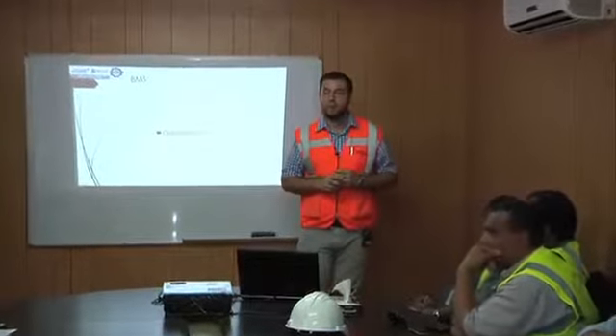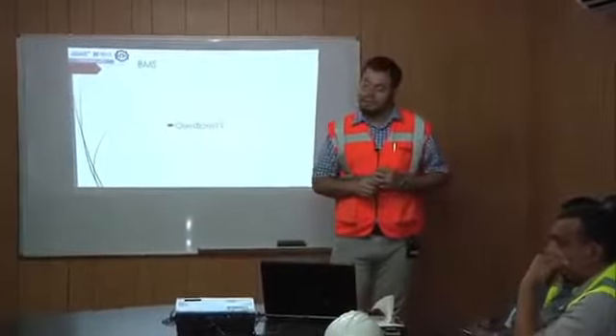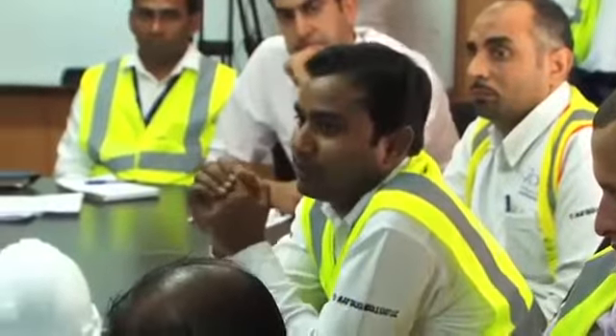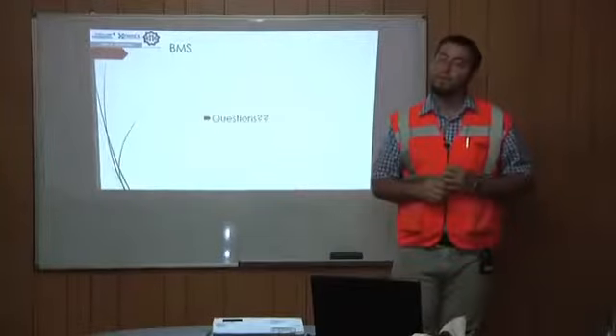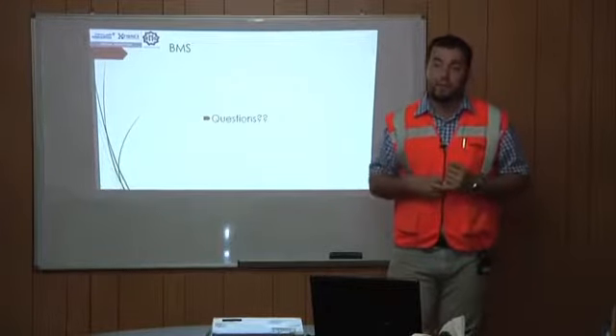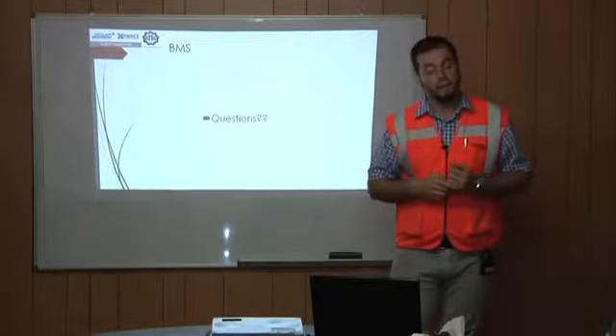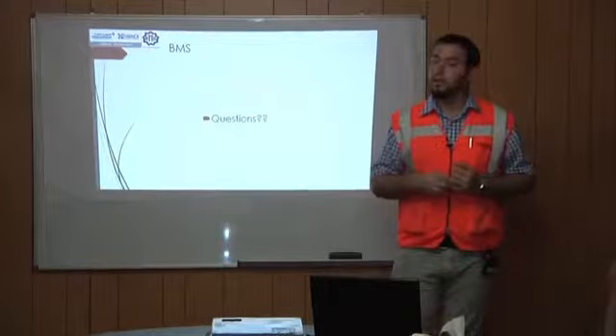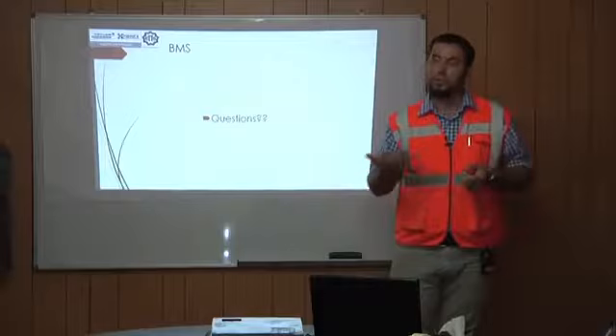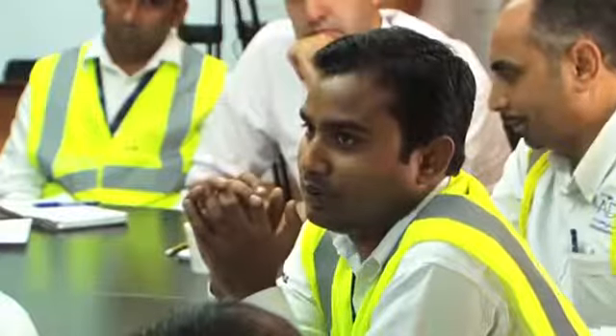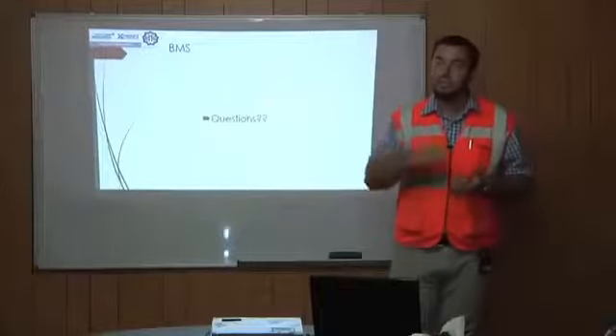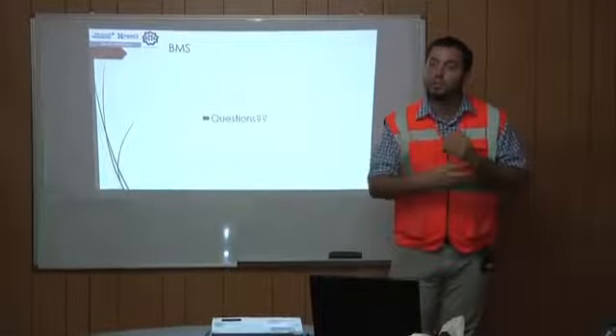Our RTUs all are connected to the BMS, right? Yes. In the supply and the return of the RTU, is there a damper or not? For the supply? For the supply, there is the supply side of it. No damper. You will not be able to, because the fan is actually controlled, so you don't need a damper on the supply, right? In our RTU, there is no damper. The VFD is controlling the motor, so it's controlling how much.